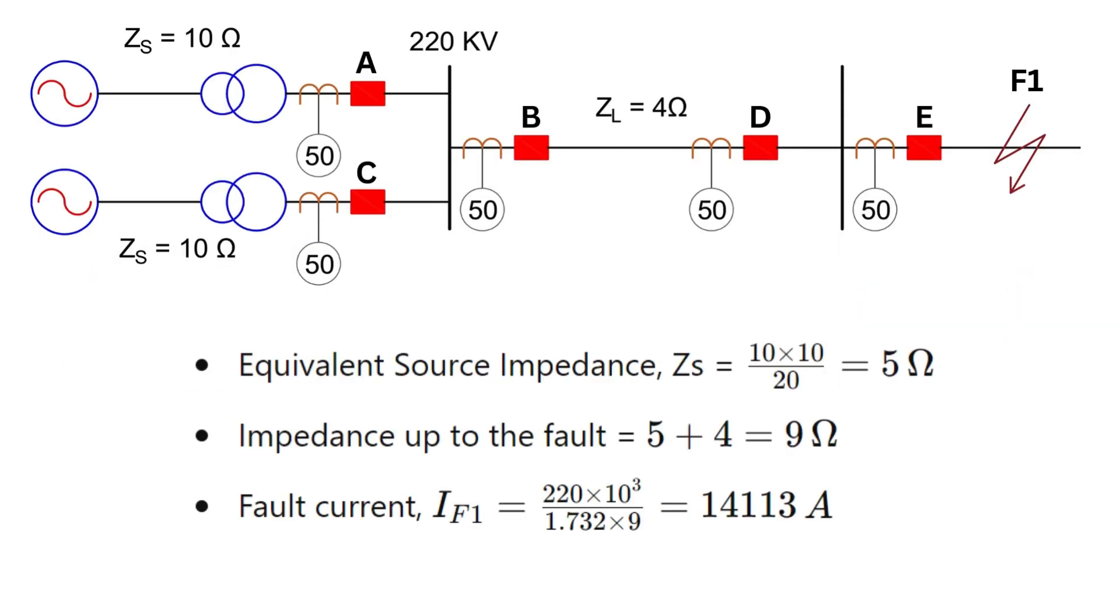For this setup, the equivalent source impedance, Zs, is equal to 5 ohms. The total impedance up to the fault point would be 9 ohms. Now, let's find the fault current at F1. IF1 is equal to 220 × 10³ divided by √3 × 9, which is equal to 14,113 amperes.